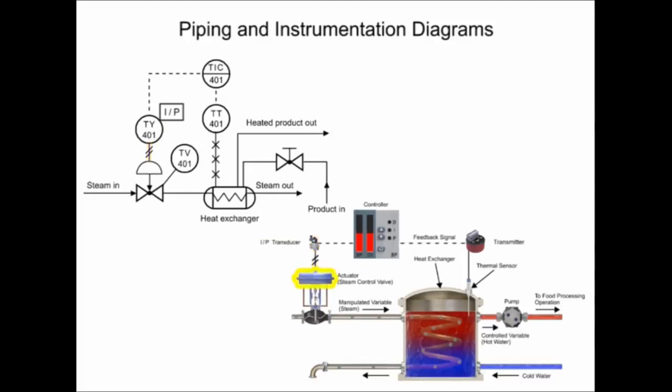The pneumatic controlled diaphragm actuator that opens and closes the globe valve regulates steam in the process. The actuator is represented by the half circle in the P and ID. The arrow pointing downwards from the actuator indicates a fail closed valve type.